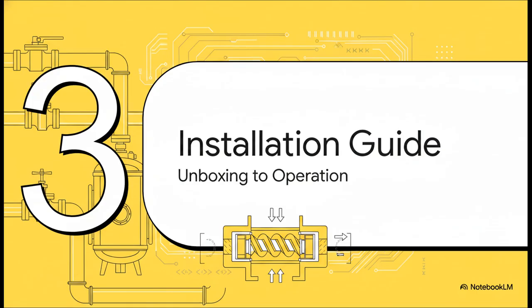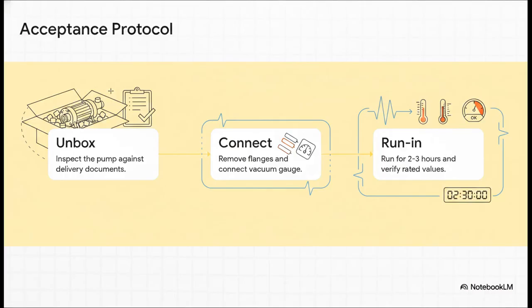All right, Section 3, Installation Guidelines. Let's get into the practical side, from unboxing to operation. A flawless setup starts the second the crate hits your loading dock. The standard protocol is pretty straightforward. Do a careful visual inspection to make sure there's no shipping damage. Then, take off the blank flanges, hook up a vacuum gauge to the inlet, and, this is key, do a run-in phase.